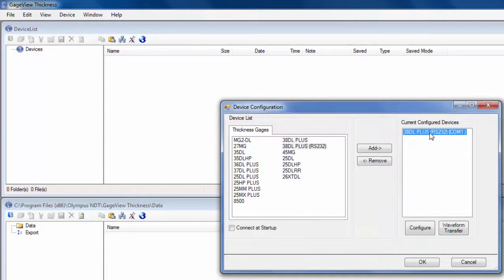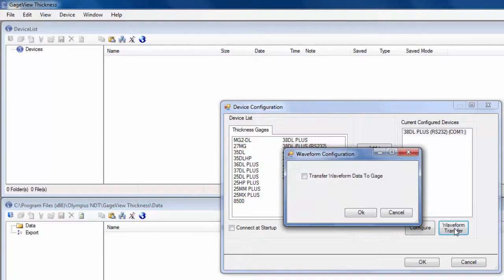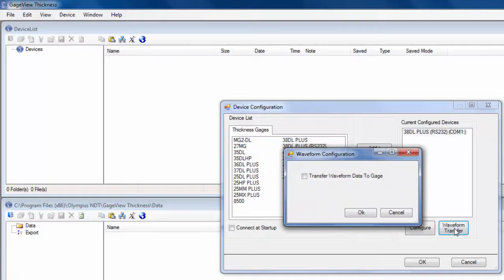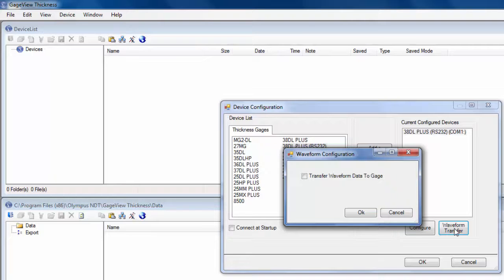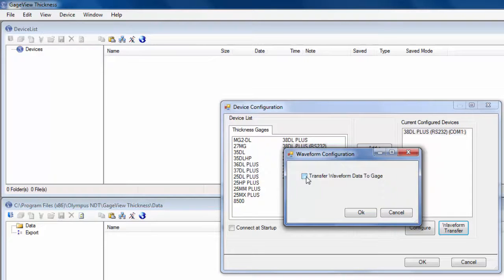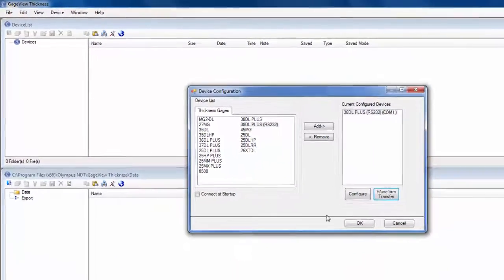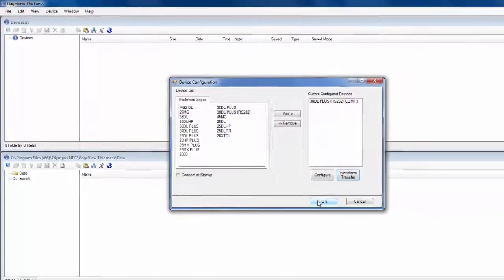Then you have the option to click Waveform Transfer. By default, if you have a file in GageView Thickness that contains waveforms and thickness data, when you transfer the file back to the instrument, only the thickness data transfers. The waveforms do not. The reason being is most customers don't need the waveforms transferred back to the unit, and also by not sending them it helps cut down on the time it takes to transfer the file. But if you'd prefer to have the waveforms transferred back, you can check off Transfer Waveform Data to Gauge and then click OK. For this video, I'm just going to leave it unchecked.